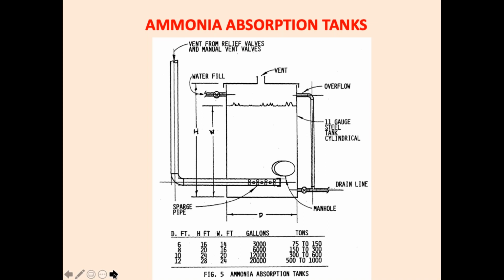I'm purposely giving the full details of the ammonia dump tank, and if you see this vent line from the relief valve or from any place can come into this tank, and the tank is full of water. So ammonia will be absorbed in water. A big amount can be absorbed, nothing will happen. And these dump tanks are very useful many times.